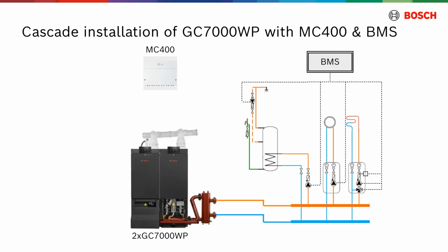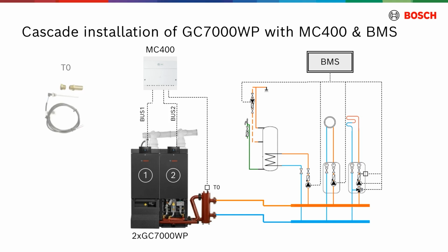To properly install the system, the first boiler must be connected to the bus 1 terminal and the second boiler to the bus 2 terminal on the low-voltage terminals of the MC400 module. Furthermore, the low loss header sensor, labeled T0, has to be connected to the appropriate terminal of the MC400. Attention! The T0 sensor is not included in the scope of delivery of the MC400 module and must be ordered additionally. An external building management system must be connected to the 0 to 10 volt terminal of MC400 module.